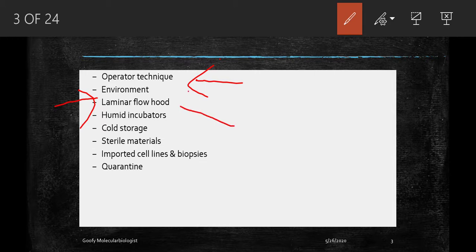The third source is maintenance of the laminar flow hood — it shouldn't be overcrowded with equipment. If your laminar flow is filled with equipment, there's a risk because the distance between the operator and the entry is reduced due to cluttering, leading to entry of non-sterile air into the hood. It can also lead to collision of pipettes. Additionally, the integrity of the filters and cabinets has to be checked at least twice a year.